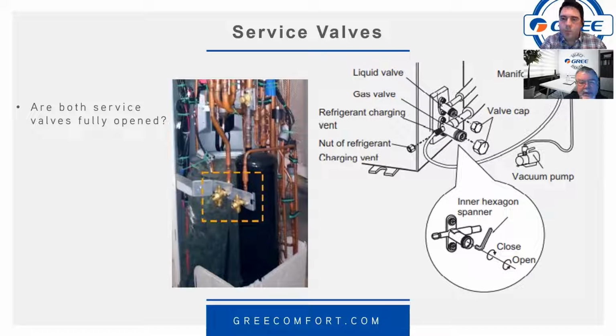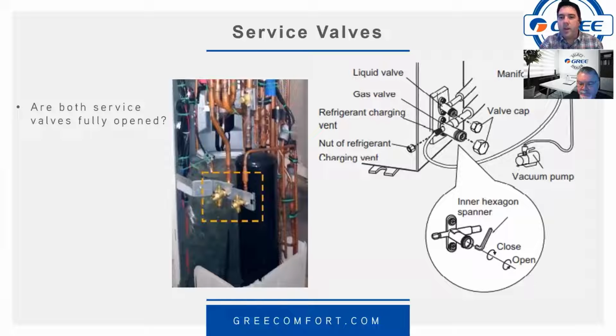Right, right. So that's a pretty important thing. You know, hearing that there's a leak in a service valve, you kind of scratch your head. And you always assume it's the connection, but cranking on those valves too hard can cause you a little problem. So something as simple as that, right? But also, the brass to brass surface of the cap that goes on it, if you torque it down closed, it will seal anything that may be behind there.